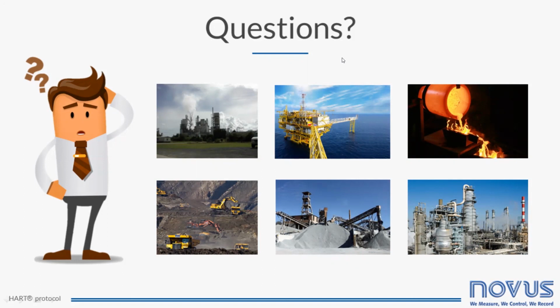I have another one. Why do I need to use a resistor? And the answer is a minimum current loop impedance is required before the HART signal can be picked up by a modem or handheld. The resistor inserted in the loop generates a minimum required voltage drop that allows communication for the HART modem. Okay.